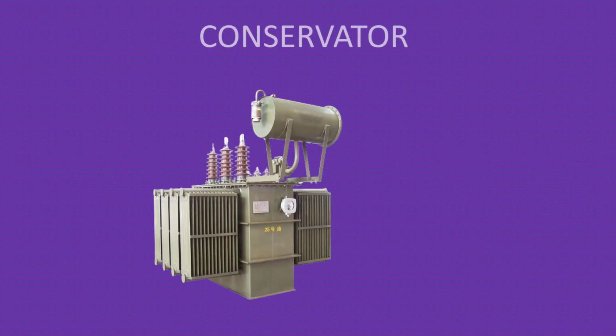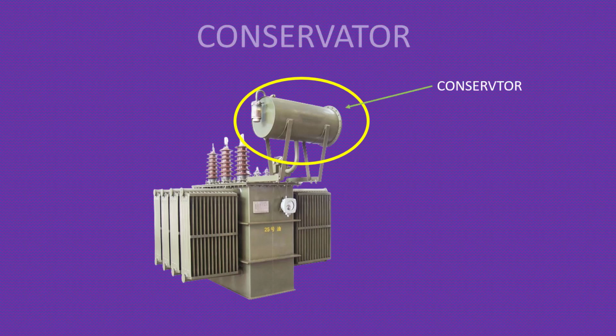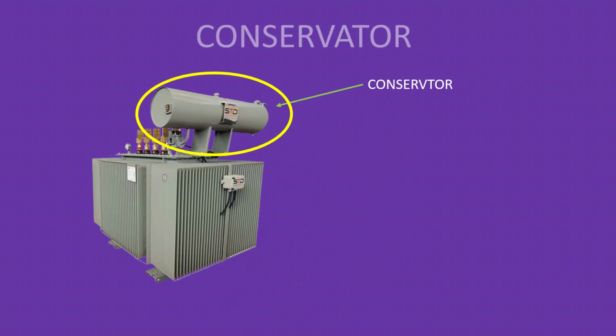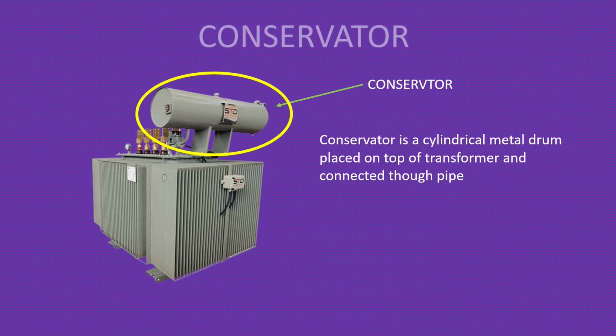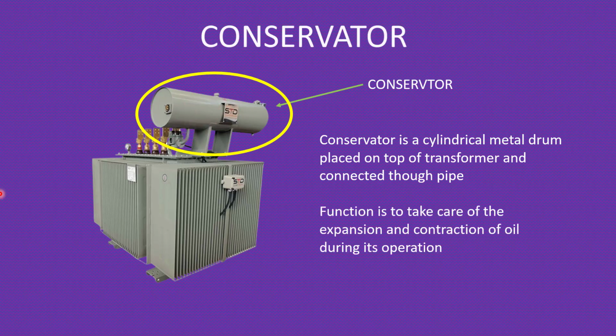What is a conservator? A conservator is a part of an oil-cooled transformer. The conservator is a cylindrical metal drum situated nearly on top of the transformer, and it is connected through a pipe. We can see this. This is the conservator, a cylindrical metal drum connected through a pipe. The function of the conservator is to take care of the expansion and contraction of oil during its operation.